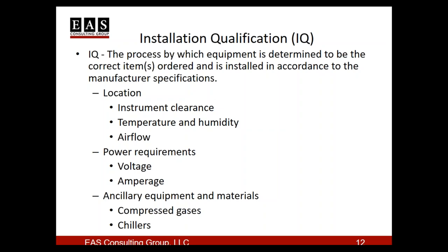Power requirements are also important - both the voltage and the amperage. GCs, for example, gas chromatographs, which we'll talk about later, usually need to operate at a higher voltage and or higher amperage because they have to ballistically heat up very quickly. Ancillary equipment and materials such as compressed gases will need appropriate lines, and of course, if there are any chillers being used, those would require water.